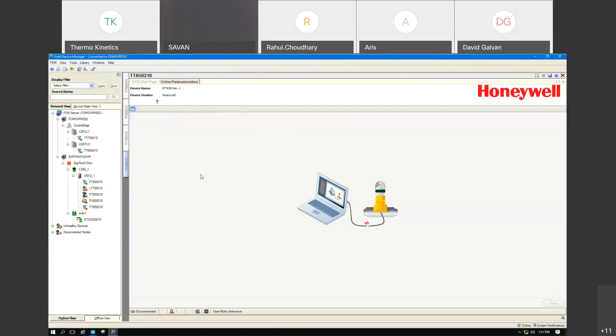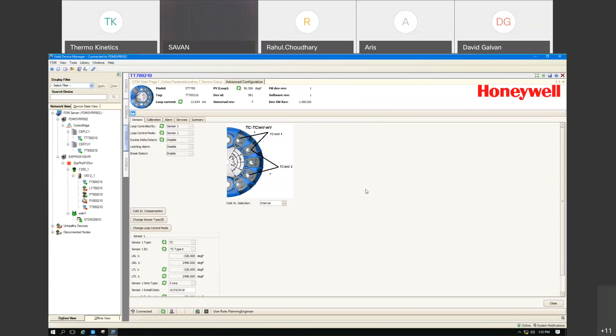So again, this is the PLC. You have your dashboard. If you want to configure the device, you go to advanced configuration, and you can do that. It shows you where to land the wires and how to configure the sensors. But the important thing is that every channel on that PLC, every channel on that RTU, the AIs and AOs and DIs and DOs, has HART ability. It's not like the traditional HART mux multiplexer chassis where you have one modem multiplexing across several channels. Every channel has its own dedicated HART modem for a one-to-one relationship.